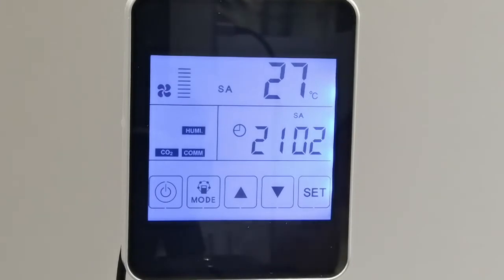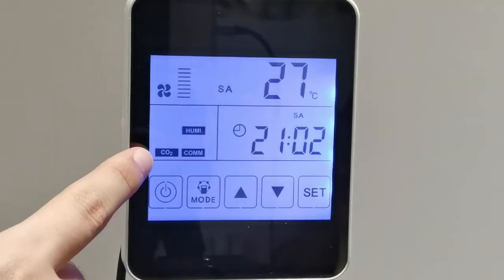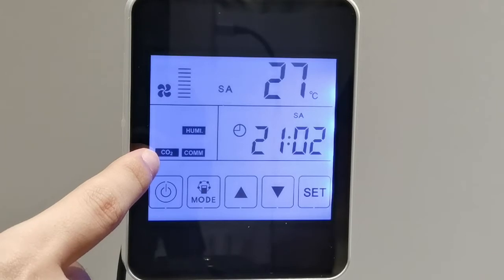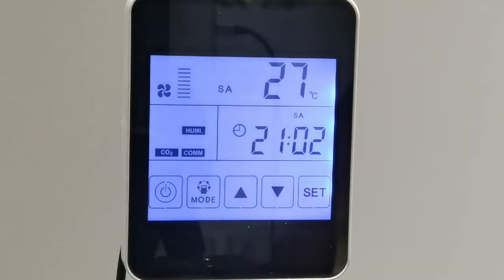The CO2 symbol appears on the panel. See, if the ERV is connected to a CO2 sensor, the logic is when the CO2 concentration is higher than the setting value, the ERV runs at highest speed until the concentration is down below our setting value.